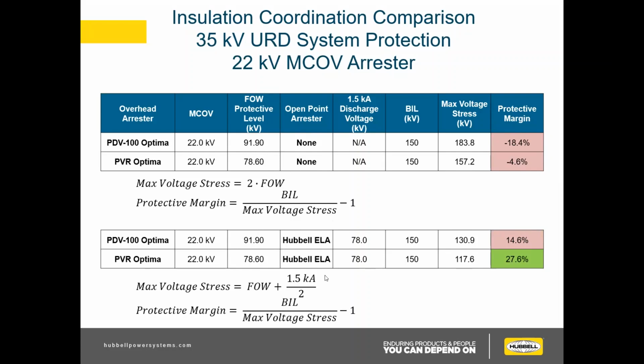So this is where, running through an insulation coordination study with us, we can really make sure you are where you're supposed to be. So here we have the elbow arrestor and an appropriately sized PVR Optima, and you are in the clear at this 22 kV.